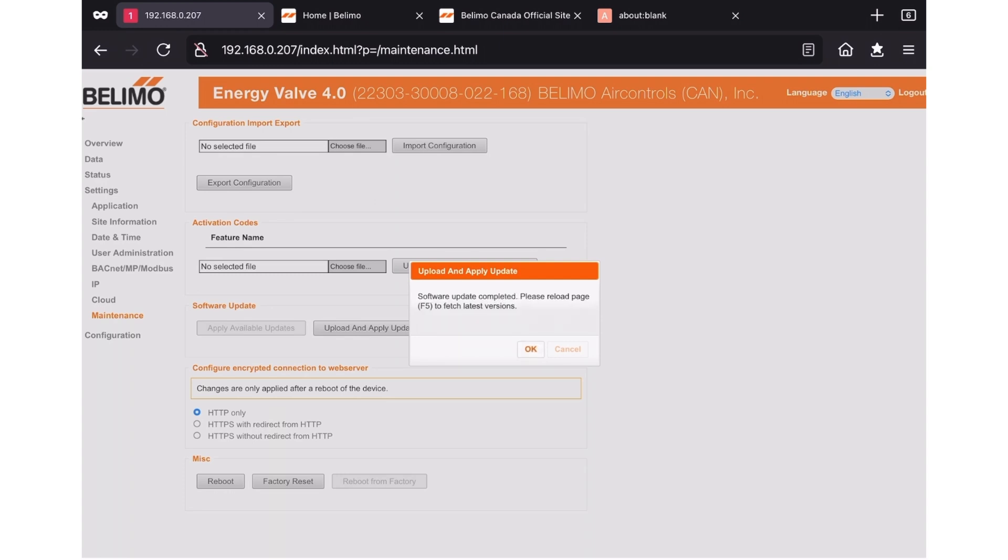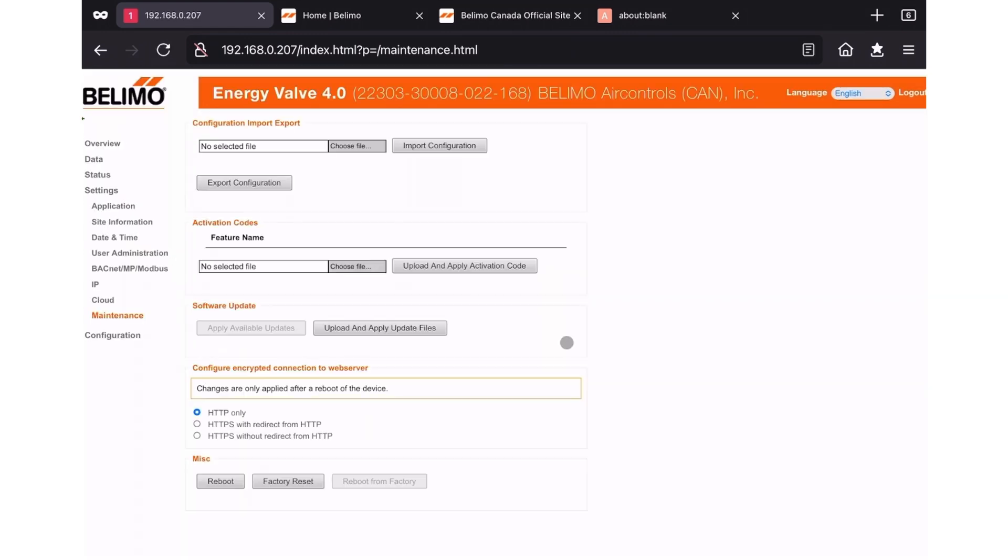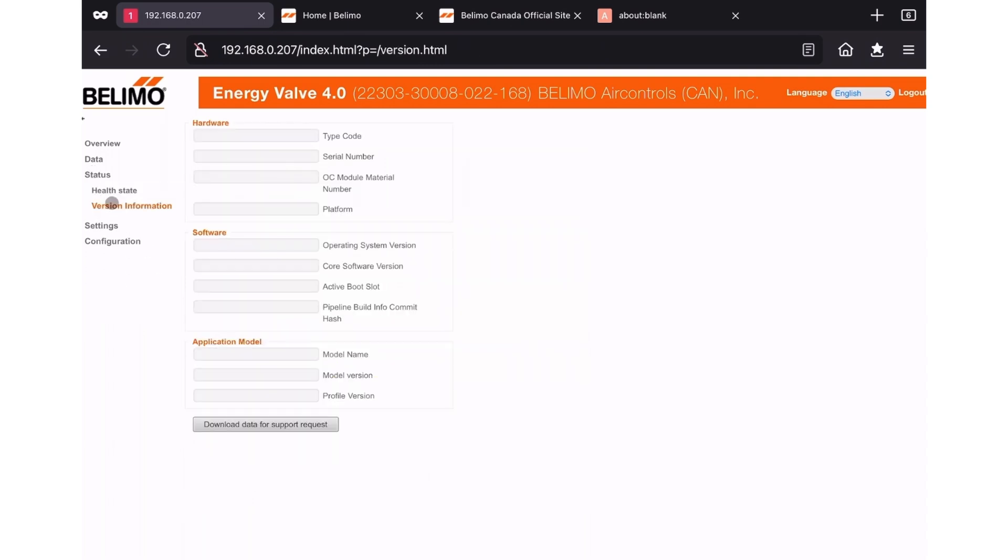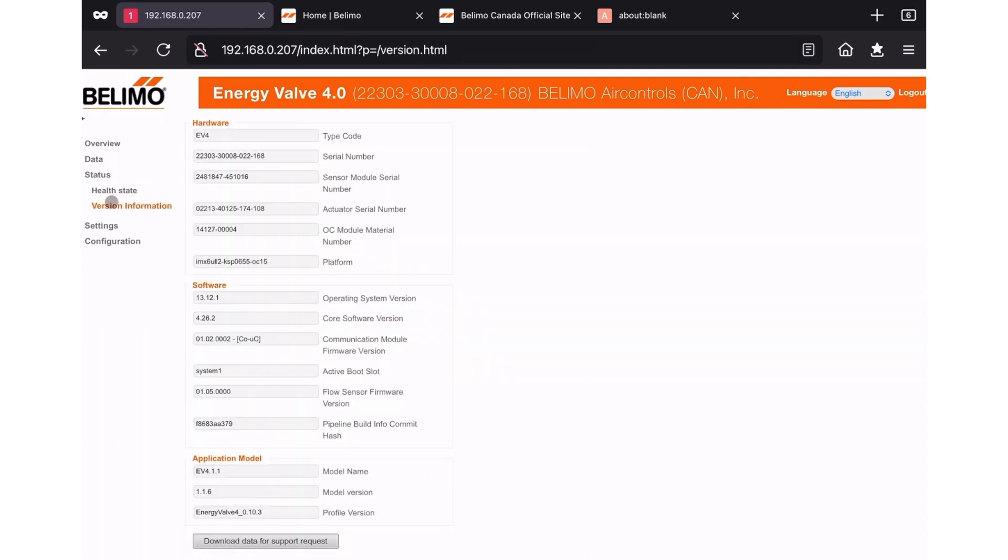Once complete, you can attempt to refresh your browser and re-log into the device. Once you're logged back into your EV or thermal energy meter, verify that the update was successful. To do this, navigate to the status and then version information menu. This will open up the new screen. Once again, check the core software version and see if that matches with the version that you downloaded from our website.